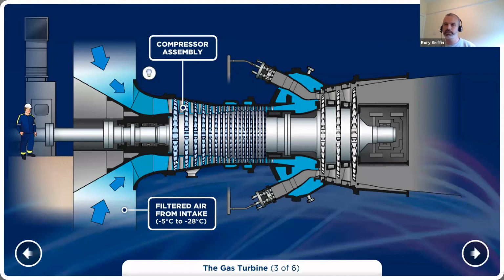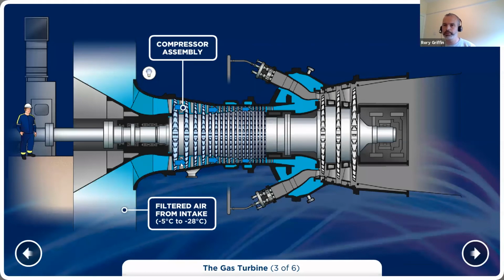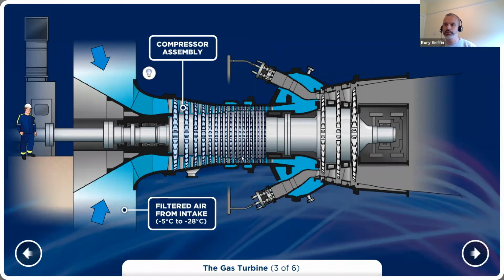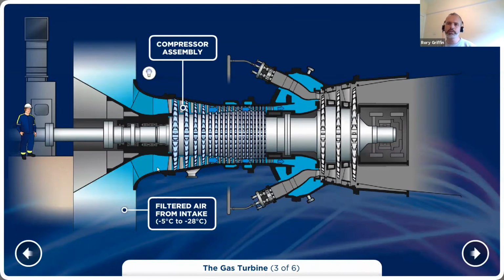So as it passes each stage, it'll go through a little set of nozzles, or other people might call them diffusers, which helps straighten the air back up. Hits the next stage, downward force again, and it keeps straightening up and getting rotated as it moves all the way down. So while you start off here at atmospheric pressure, maybe just a bit down from it, by the time you get to the end of the compressor section here, the discharge pressure is up maybe at 17.5, 18 bar pressure.